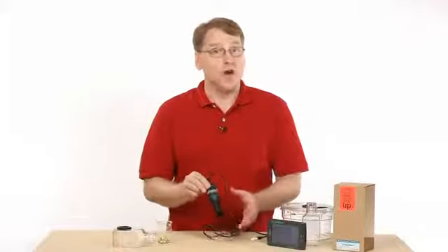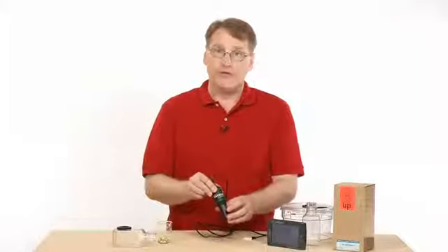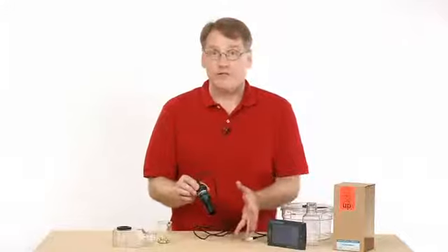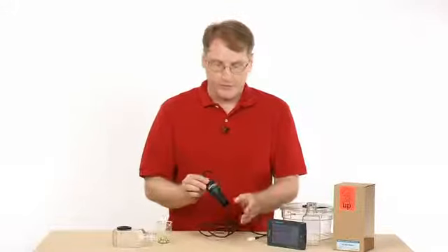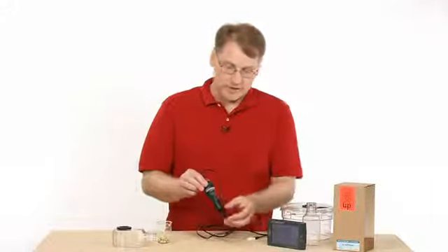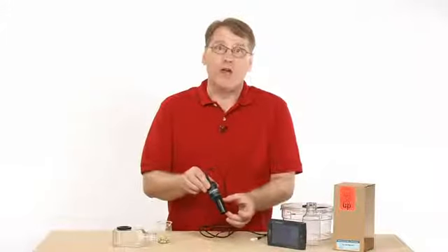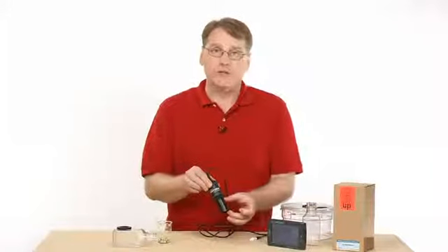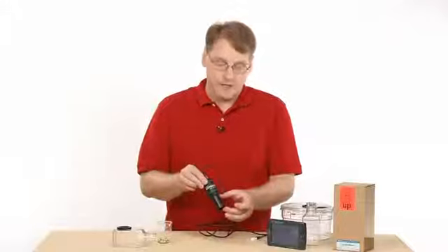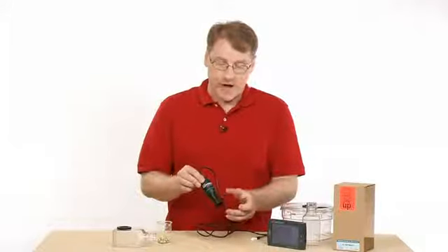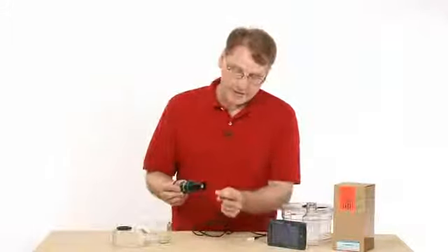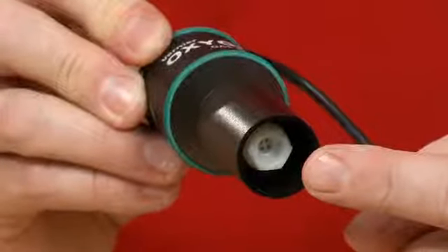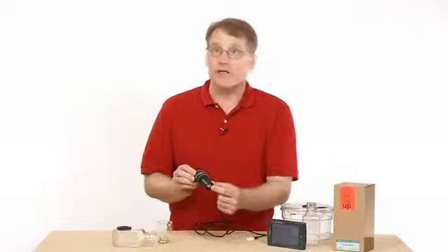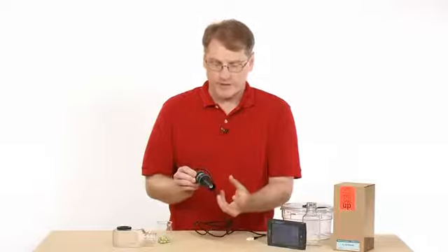It's not for dissolved oxygen, so you do not put this into a liquid. We do have a dissolved oxygen sensor, but it's not this one. And the way this works, it is a chemical half cell, and it measures the concentration 0 to 27% of oxygen. And the oxygen has to go through a membrane here at the bottom. So it diffuses through there, and it can measure that concentration.